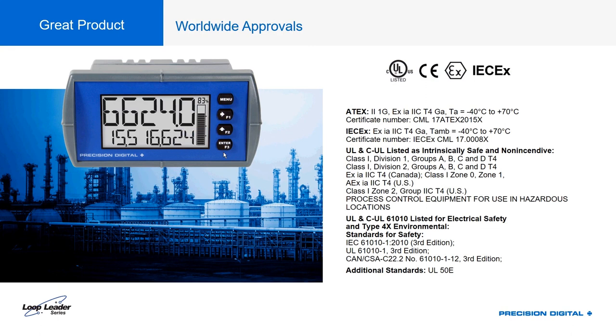Worldwide approvals are a major draw for loop-powered devices, which can achieve intrinsically safe and non-incendive ratings at a much lower price than equivalent explosion-proof devices. The Loop Leader carries ATEX, IECEx, and UL/cUL intrinsically safe and non-incendive approvals for hazardous areas, as well as UL and cUL general electrical safety listings for safe areas — covering both general panel shops and hazardous location requirements.